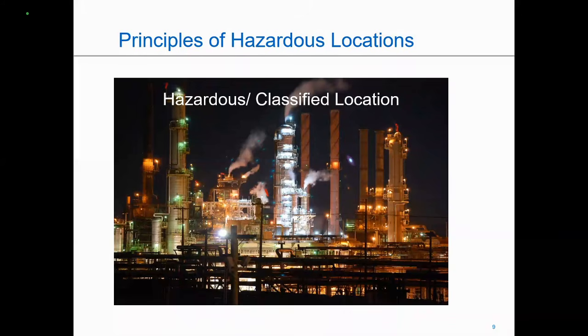It could be a case where we get a particular product that is approved and certified, but it's an overkill, or we may actually get a product that is just flat out a code violation to install in that area. So for example, when I have an area with combustible dust, explosion-proof equipment is not automatically approved for a combustible dust area. There is some explosion-proof equipment that is certified for use also in a combustible dust area, but there is some equipment that contains certifications for only gases and vapors and not for combustible dust. So in that case, it'd be a code violation to use that in my combustible dust area. So again, explosion-proof is one of the methods of protection. We work in hazardous areas, we work in classified areas.